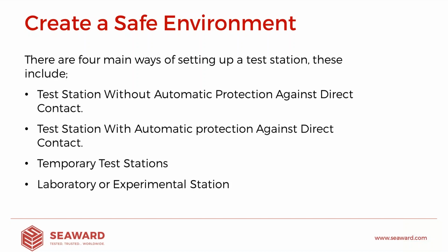Both of those really come into play in certain environments where it may not be practical to set up one of these type environments, or we may have large products that we need to move the test area to the product rather than the other way around. But we're going to traditionally focus on the first two, the test station with and without automatic protection, because both of those play a factor in how you would set up an area for temporary test stations or indeed laboratory type environments.